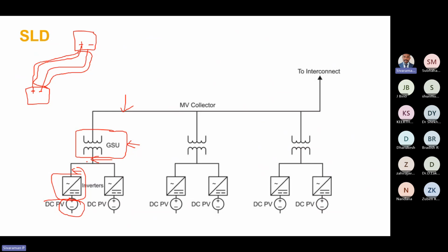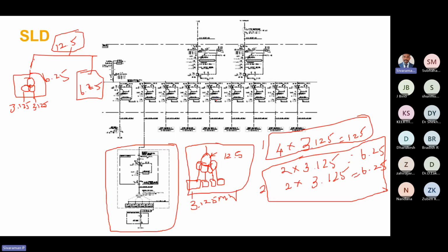The AC cables we are using connect the inverter to the inverter duty transformer, and cables are used in the collector network. These are all the cables where we can expect losses. We can expect a larger amount of losses, so we have to consider that also.